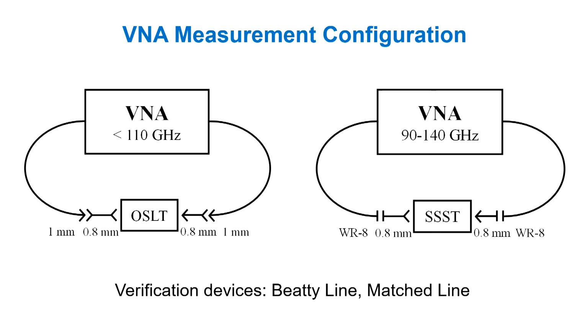Then for the high band with the offset shorts, we had another VNA that had WR8 test ports. So we were able to make measurements on that from 90 to 140 gigahertz. And we had adapters to get us to 0.8 millimeter. So we've got measurements up to 110 for OSLT and 90 to 140 on the offset shorts. So that gave us actually from 90 to 110 gigahertz, we have some overlap, which was kind of nice, so we could see how well our 2 calibrations were doing. And then in addition to calibrating these 2 VNAs with the different calibration kits, we measured our Beatty line and match line on both of these VNAs.